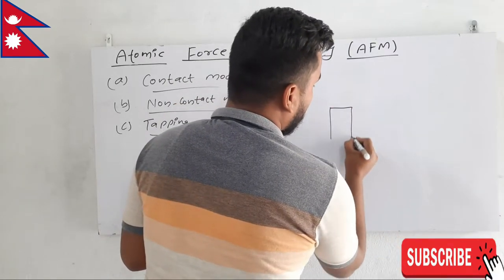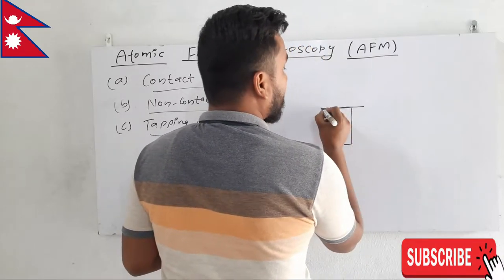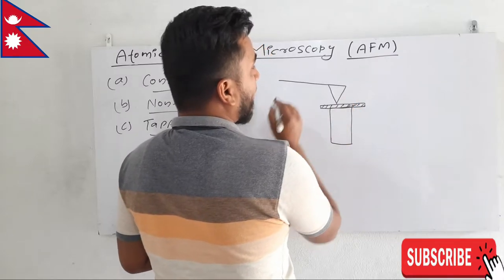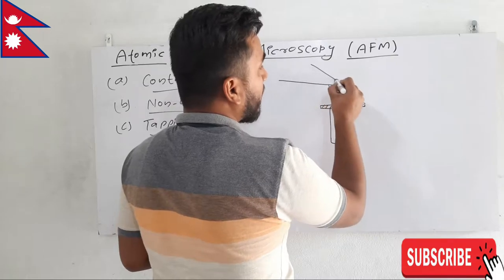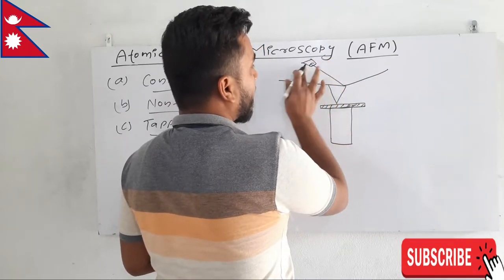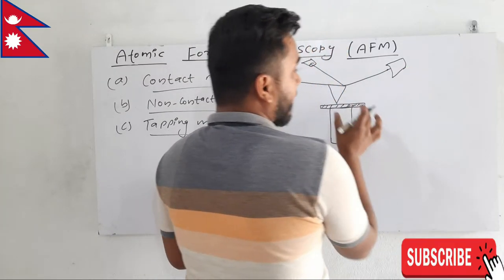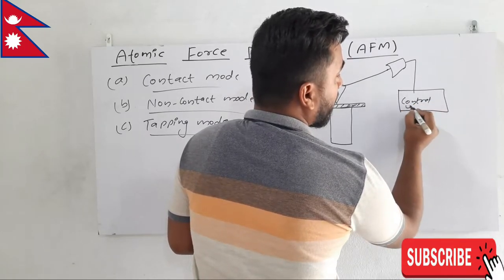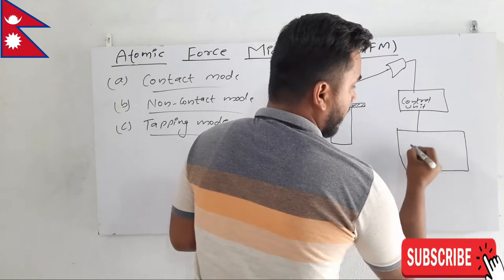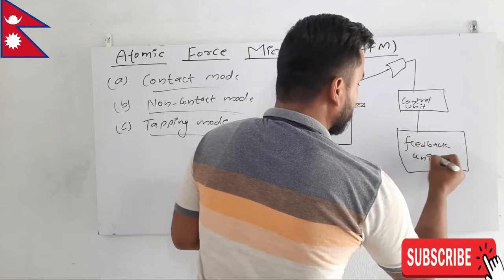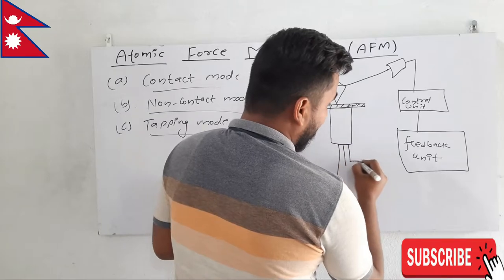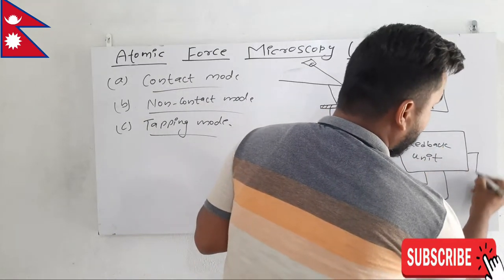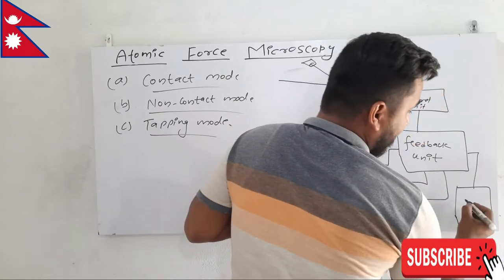First of all, there is a piezoelectric scanner, and the sample is placed on it. There is the cantilever, and the movement of the cantilever is observed by a laser light. The signal from the laser is detected by a photo detector, which is transmitted to a control unit and then to a feedback unit. From the piezoelectric scanner, three electrodes come out and connect to the feedback unit, and from the feedback unit the result is transferred to the display unit.